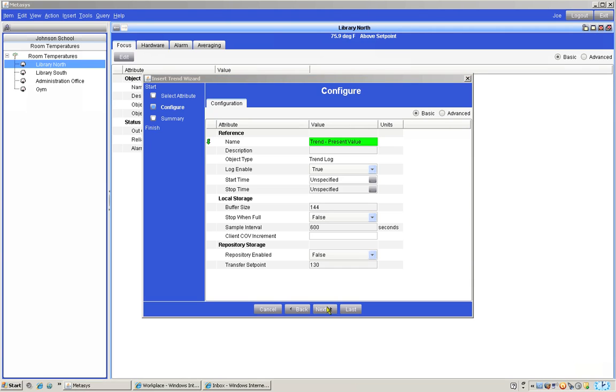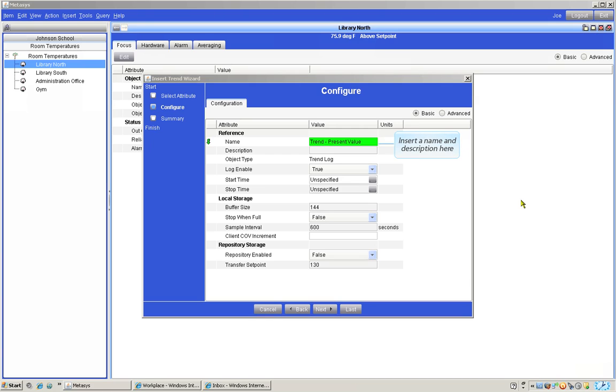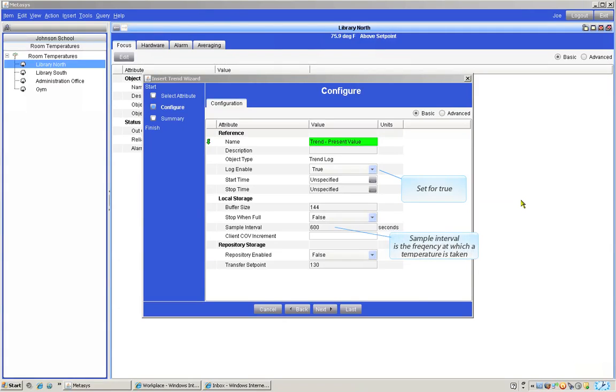In the configure window we will set up how the trend will function. There are many variations and choices available as to how we want a trend to work. The help system can help you with details. In the configure window we can name the trend whatever we would like. You may even use a description in the description box. The log enable area must be set for true in order for the trend to function. We will leave most of the settings in this window alone.